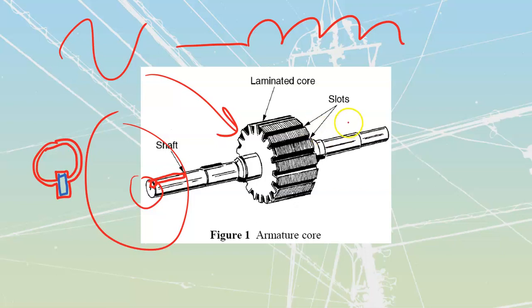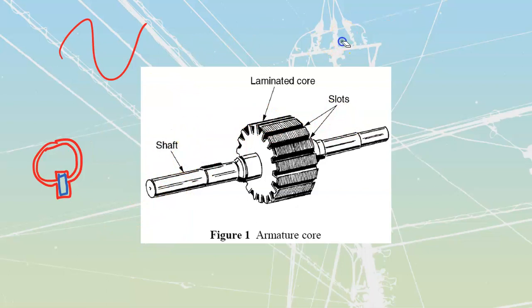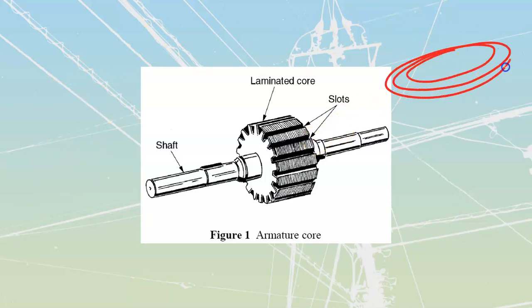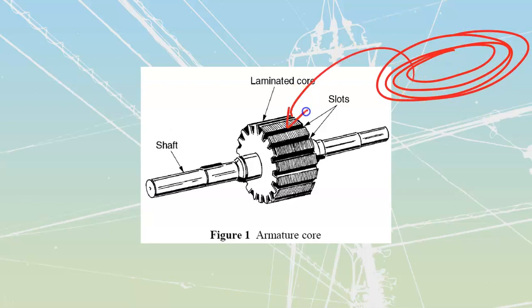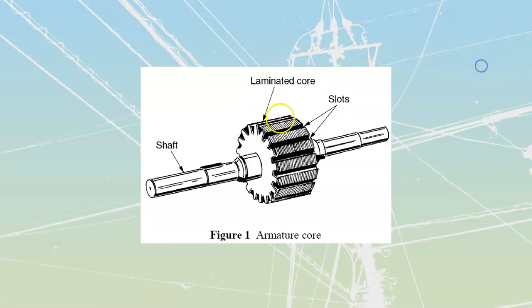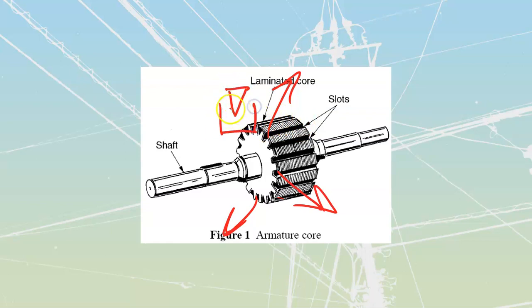Once we've built the laminated core, we take windings of wire. They're usually not wound around the core while it's in place — the windings are made separately using a machine with a jig, then pressed over top of each slot. In many cases they're separate ones with the ends soldered together inside the machine, though sometimes they're contiguous all the way through. Once inside, we wedge them in place because centrifugal motion tends to pull them to the outside as the armature spins, so a small plastic wedge pushes and locks the wires into the gap.